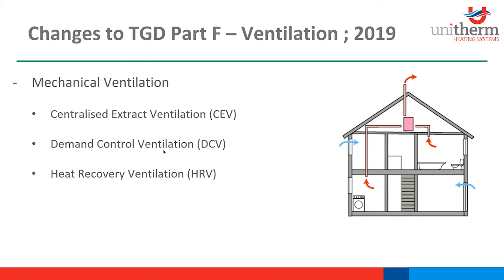Demand controlled ventilation. So this extracts from your wet rooms when a humidity sensor is triggered. So there'll be a humidity sensor in your unit or in your ducts. And when this meets your relative humidity set point of usually around 60% RH, it just boosts the fans then to bring it down to ideal thermal comfort of 45 to 55 RH. Heat recovery ventilation then is probably the most popular one, especially for single-use homes. This extracts warm air from your wet rooms while heating the fresh air from outside to your supply rooms. So I'll just talk to you a bit more about that in the next slide.